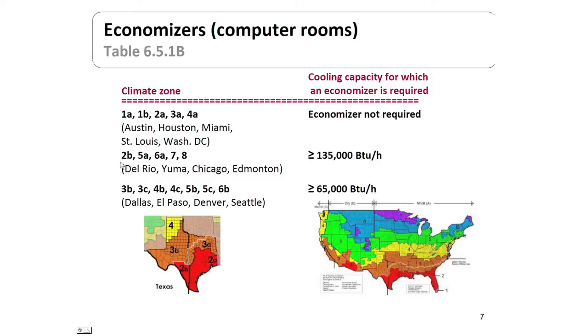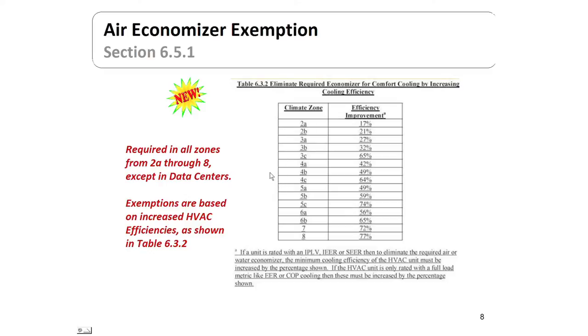Where it is required for computer rooms is in climate zones 2B, 5A, 6A, 7, and 8 if the system is over 135,000 BTUs per hour. Further north, it is required in those climate zones for systems that are 65,000 BTUs per hour or more — that's 5.5 tons of air conditioning. The exemptions are based on getting a better efficiency for the system itself. In climate zones 2A through 8, if the efficiency of your HVAC system is improved by the percentage shown for that climate zone, you would be exempt from the economizer requirement.